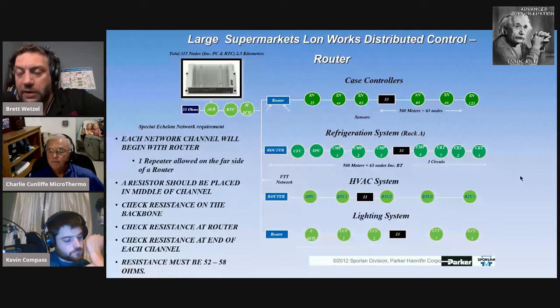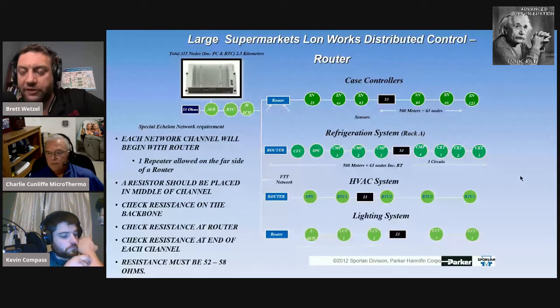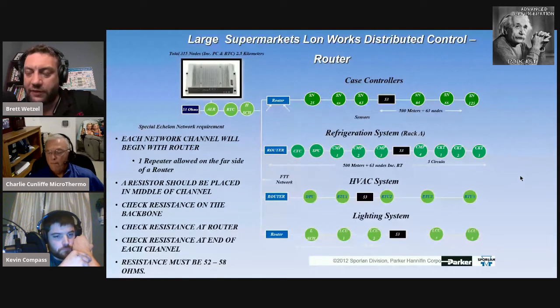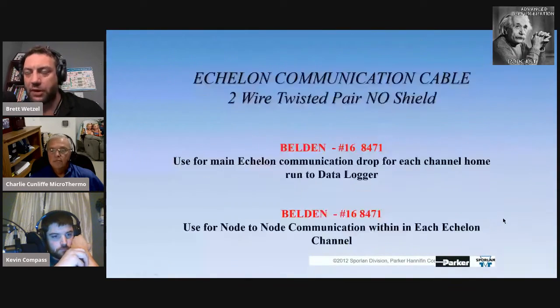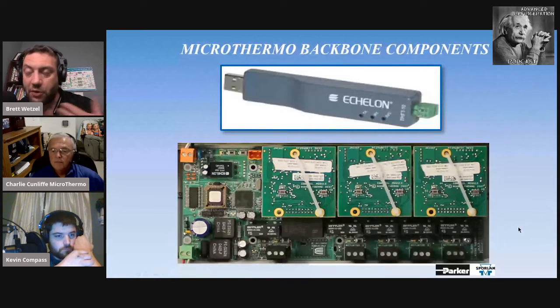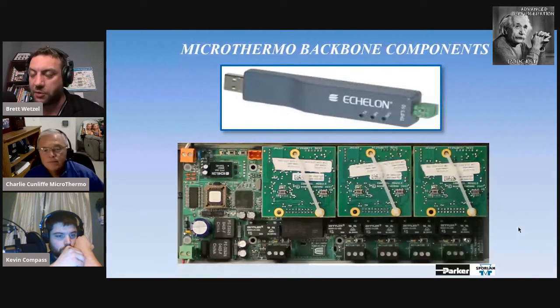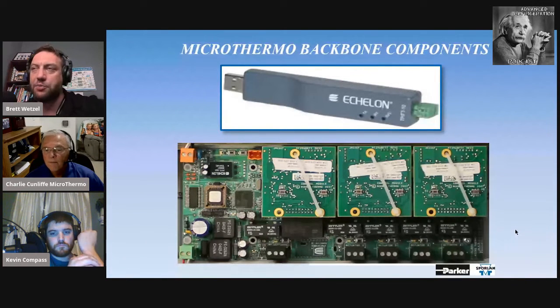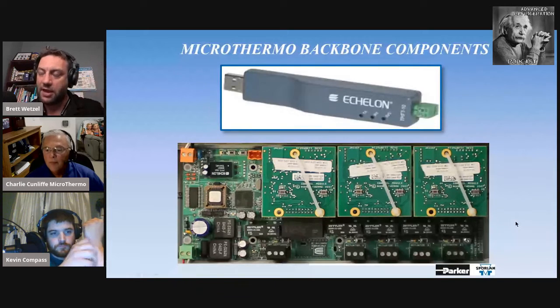There's something Charlie said I want to make sure you understand, about hitting the service pin. On Echelon devices there's what's called a neuron ID, basically like a board address, programmed into the controller by typing in the node address.